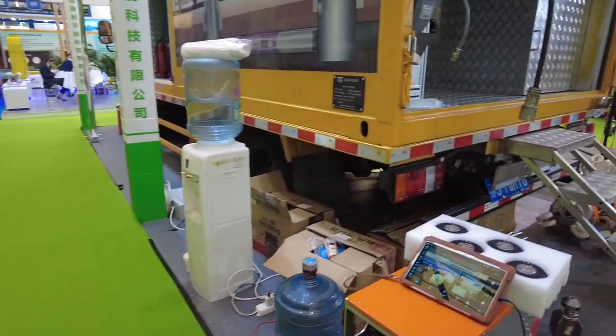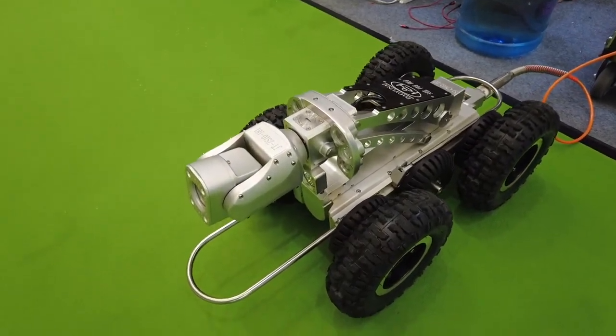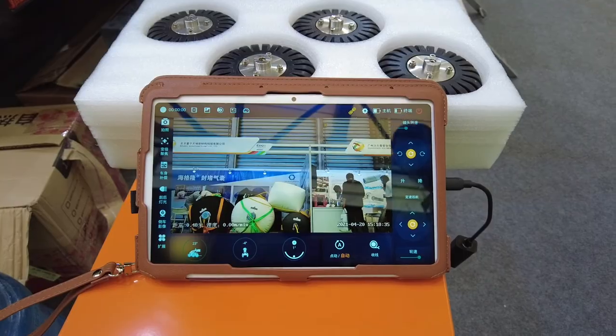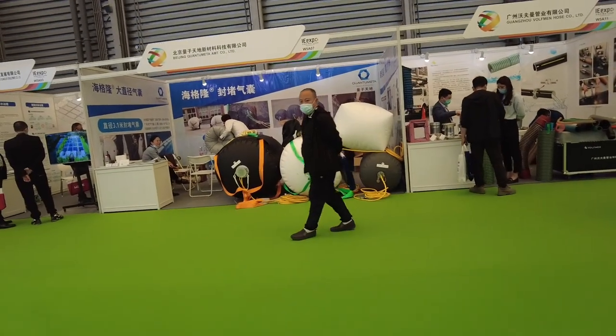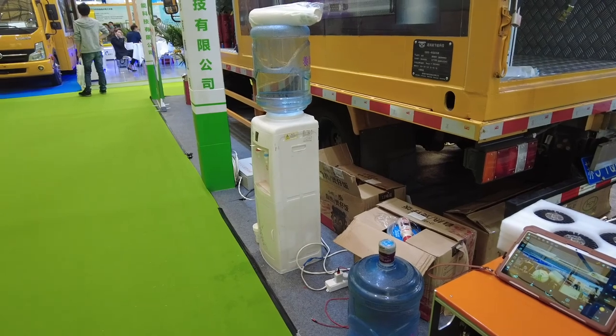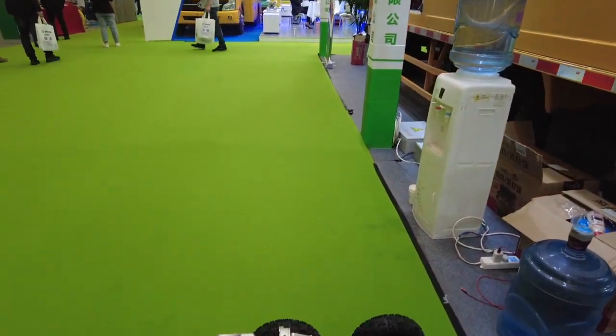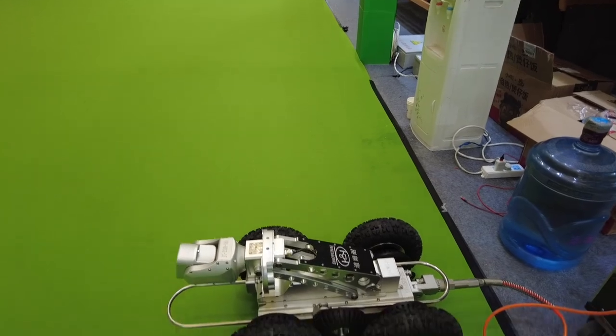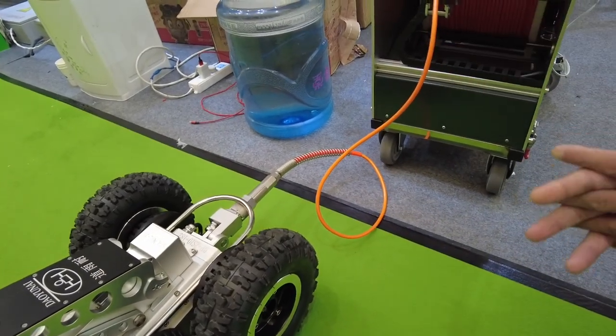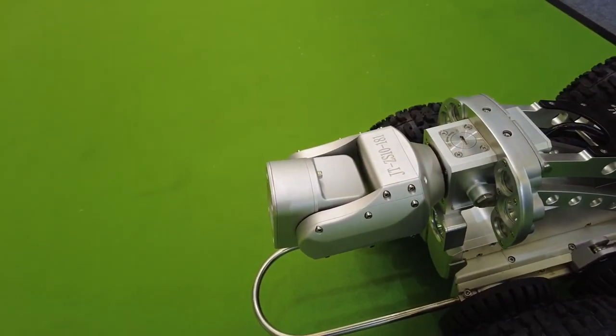哎，你这个，这个是干什么的？管道检测。对，管道检测机器人。So this is a robot to inspect the pipes. You can see the video. It's taking a video of that side, and it's actually very clear. 所以这个是检查管道内部的缺陷、破损、渗漏。See if it's got any leaks or holes. 在原有的地下管道里边，so in an existing water pipe system underground。那它能跑多远？要看绳子，这个线缆是150米。So it has 150 meter cable.